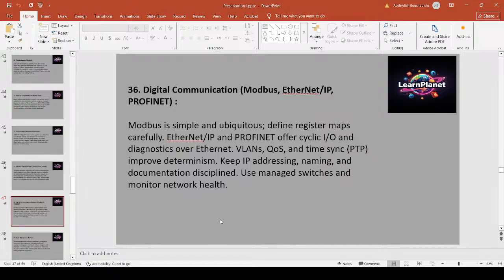Digital communication: Modbus, EtherNet/IP, Profinet. Modbus is simple and ubiquitous. Define register maps carefully. EtherNet/IP and Profinet offer cyclic I/O and diagnostics over Ethernet. VLANs, QoS, and time sync PTP improve determinism. Keep IP addressing, naming, and documentation disciplined. Use managed switches and monitor network health.